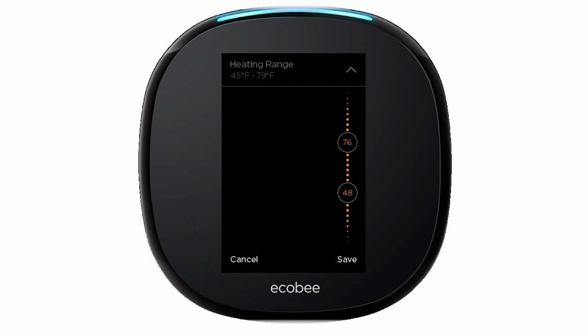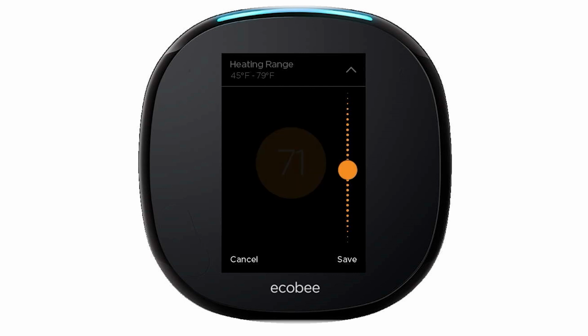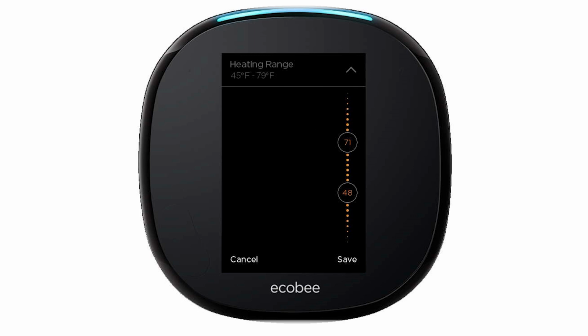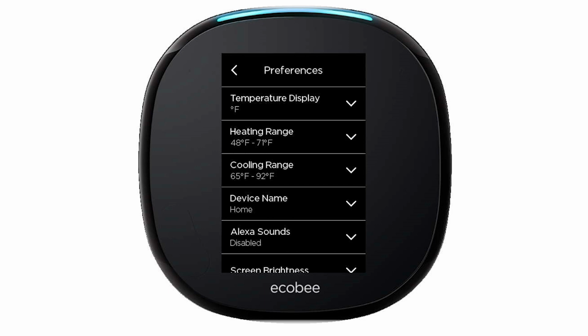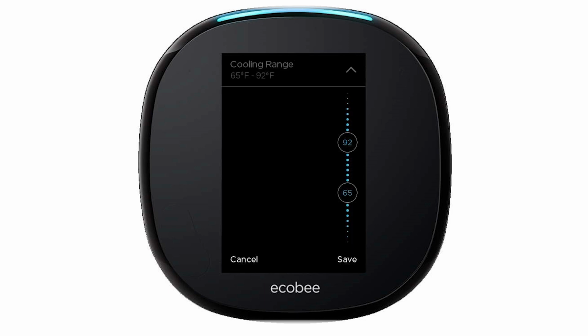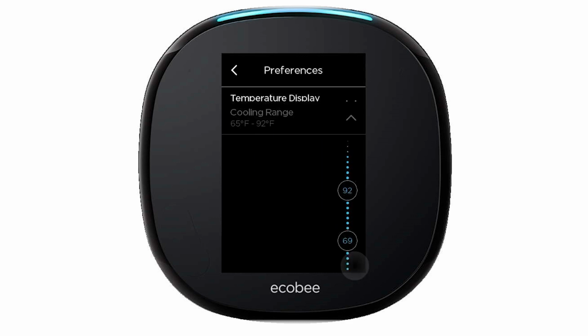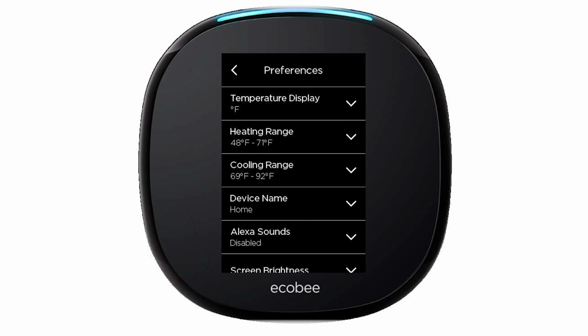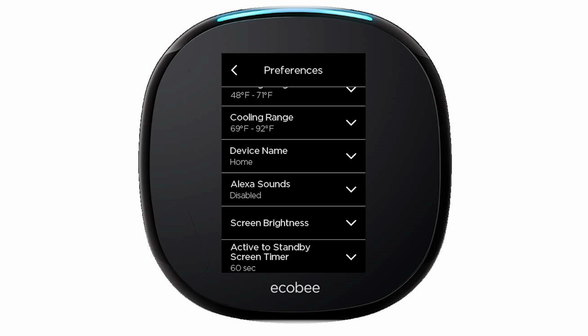So this is going to say, okay, I never want the user to adjust the set point above 71 degrees in the wintertime, right? That's warm enough. We don't need it any hotter in the house. Same with the AC. If you never want it to cool below, let's say 69, 70 degrees, that's where you go in, you'd save that there. It's going to lock the user out from running the equipment past that point. So they'll never be able to cool below 69.